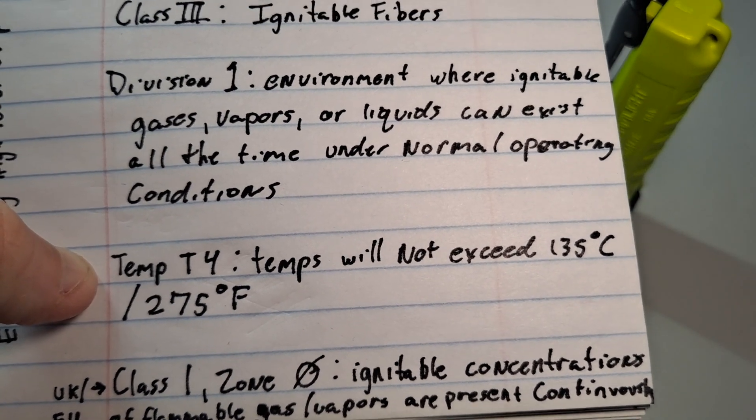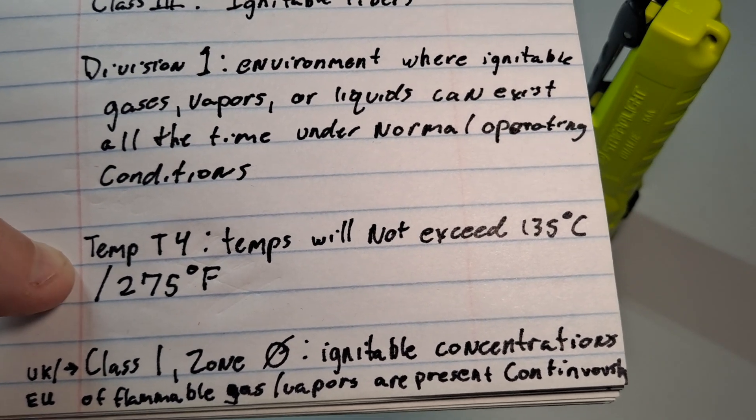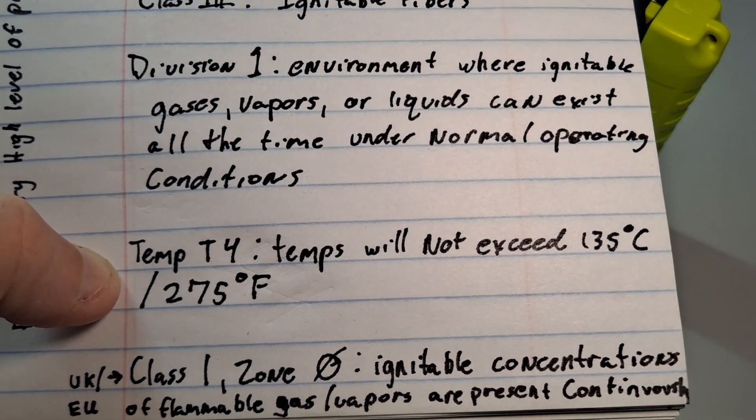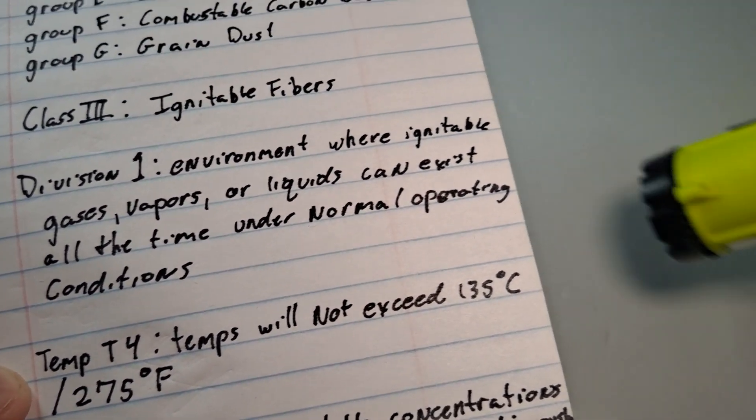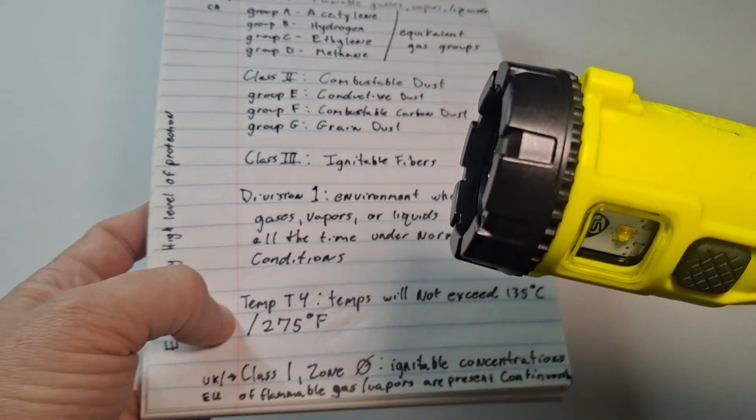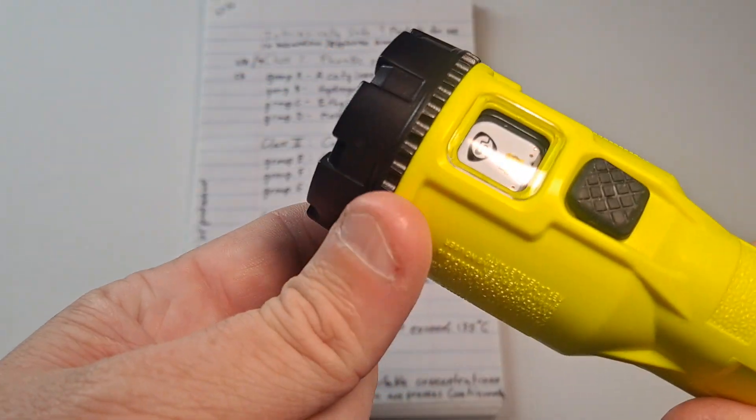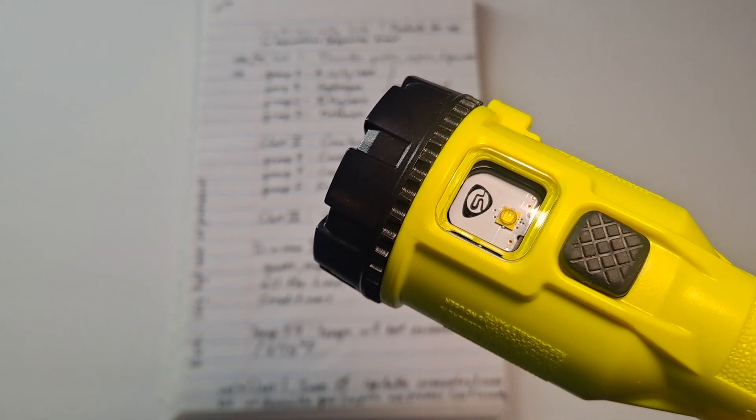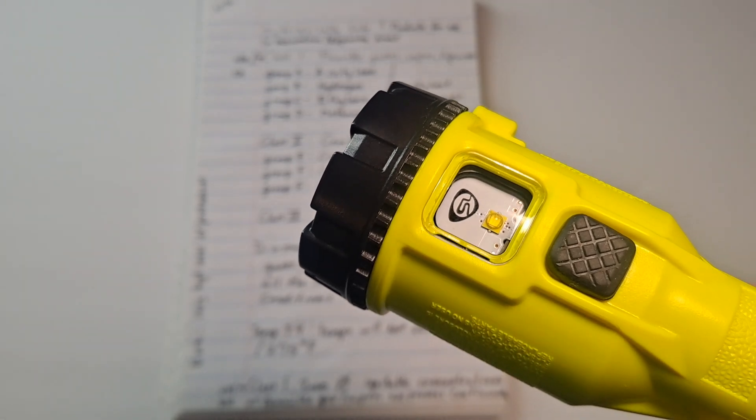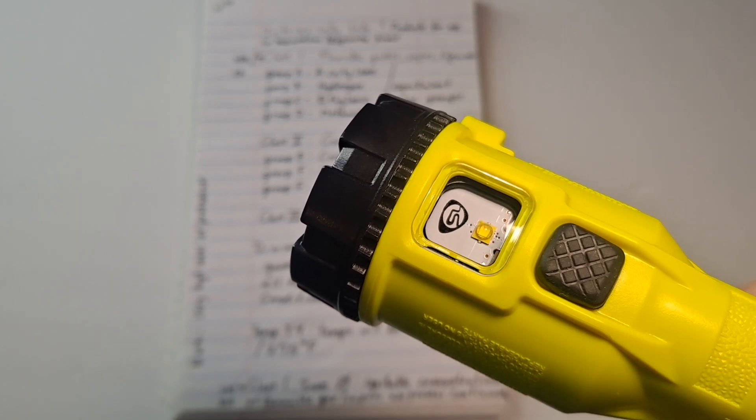Now temperature T4. The temperature T4 code regards to temperatures will not exceed 135 degrees centigrade or 275 degrees Fahrenheit. So what is that about? Well, the reason why this is low lumens, even though they're LEDs, is because a typical LED flashlight gets hot. It usually gets hot right around the ring, wherever the heat sink is on the inside. This is only rated to less than 135 degrees centigrade or 275 Fahrenheit. So this in itself should be low enough not to cause a fire.